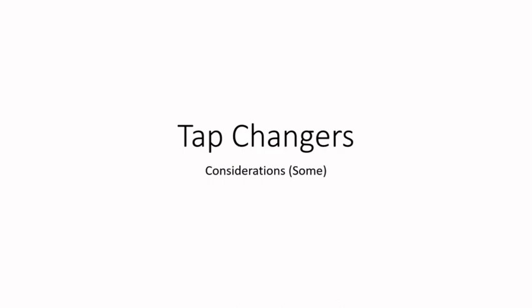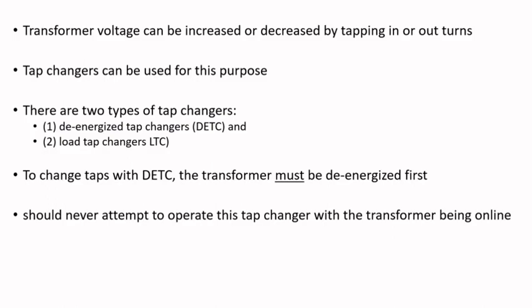In this short video I'll talk about some considerations regarding tap changers. Transformer voltage can be increased or decreased by tapping turns in or out. If we go back to the formula, the secondary voltage is the number of turns in the secondary divided by the number of turns in the primary, times the primary voltage. So you can change taps — adding or removing turns from the circuit — to change the voltage. That's why tap changers are used.